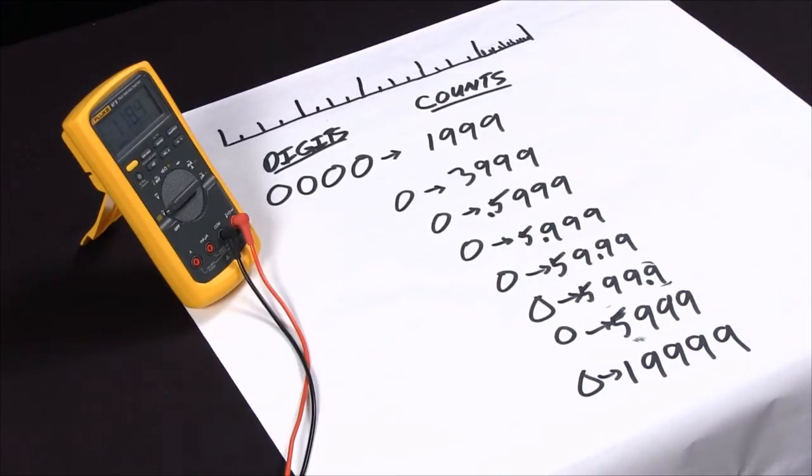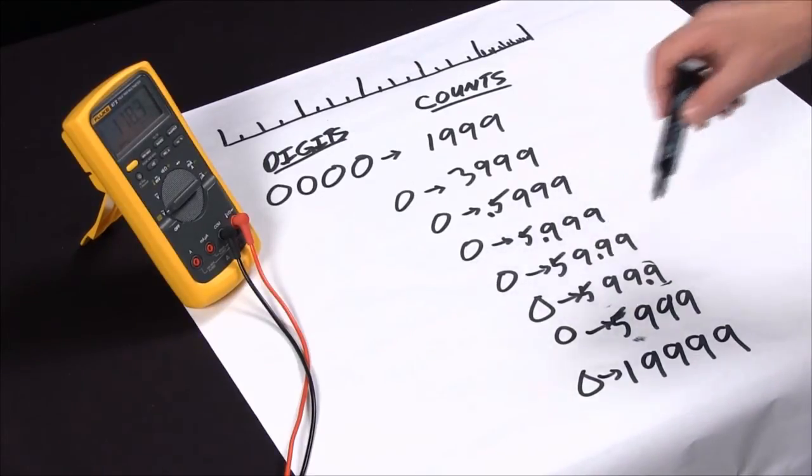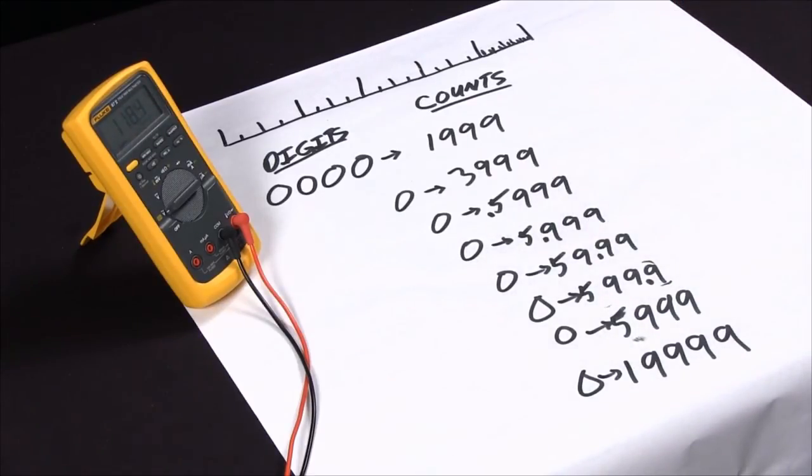So to find the resolution on a meter, simply find the number of counts and start marching a decimal point through it and you'll see what your resolution is on a particular range.